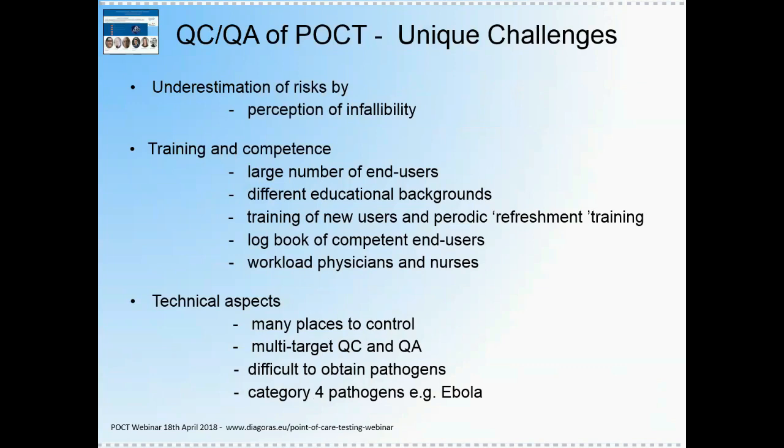And we also have to train and provide competence for the people going to use the test. Training and the management of competence can be dependent upon the number of end users and the different educational backgrounds, let's say between a doctor and a nurse. The training has to be periodic. There also have to be refresher trainings. We need to have a logbook somewhere of competent end users.